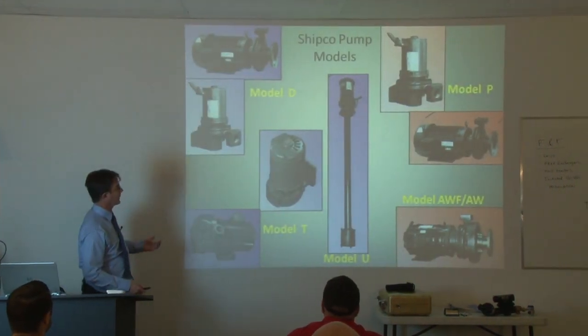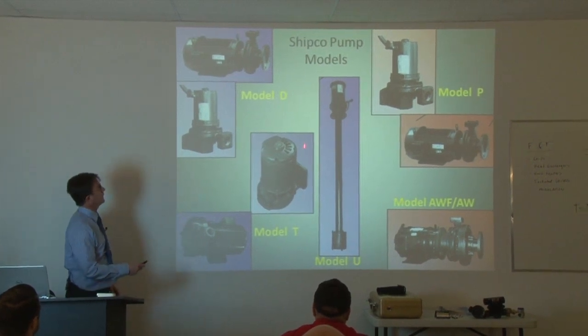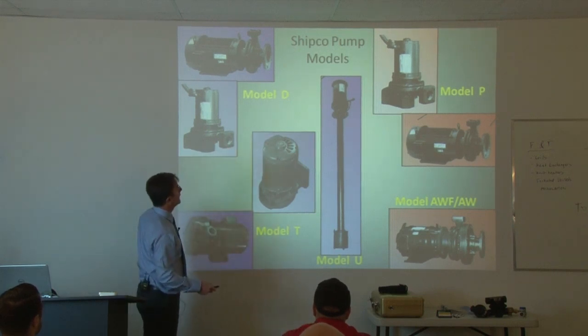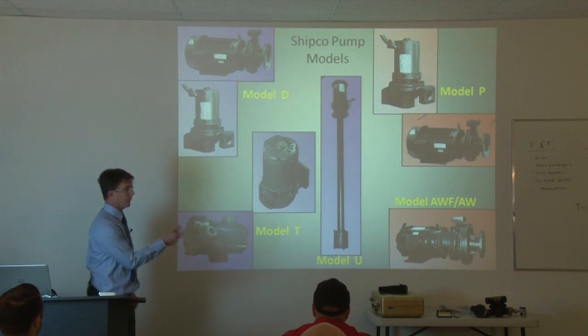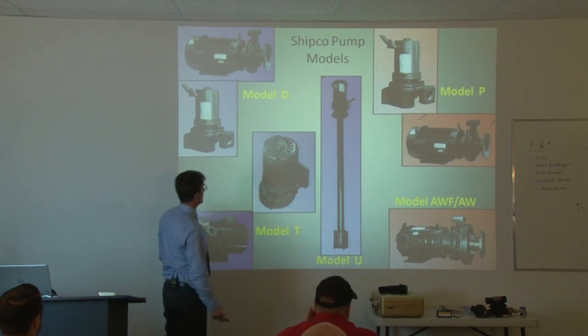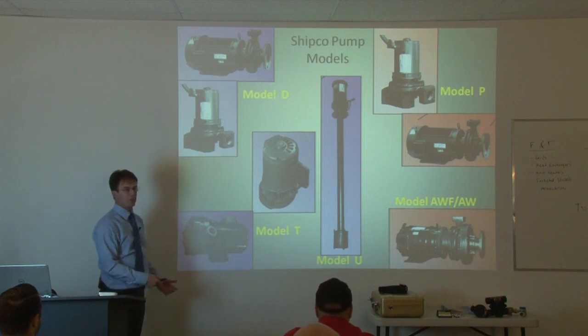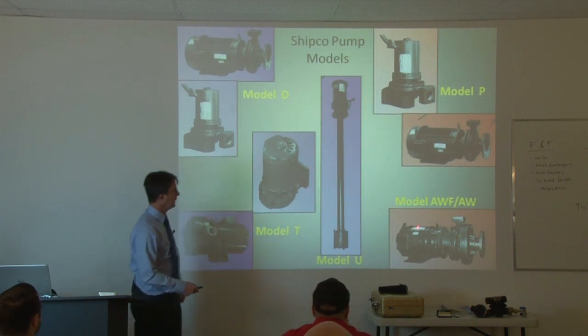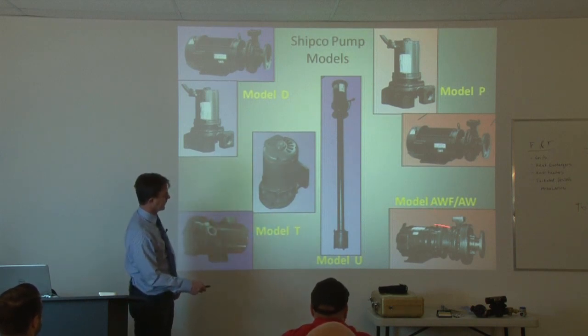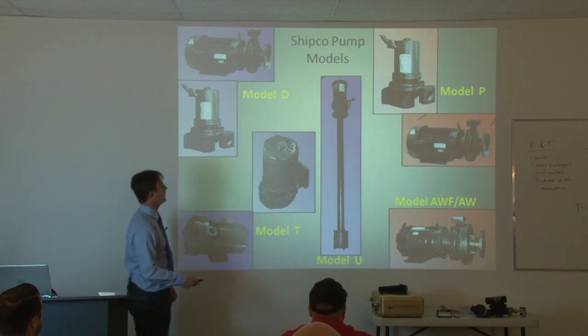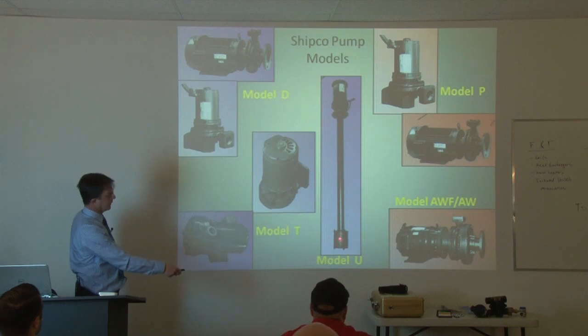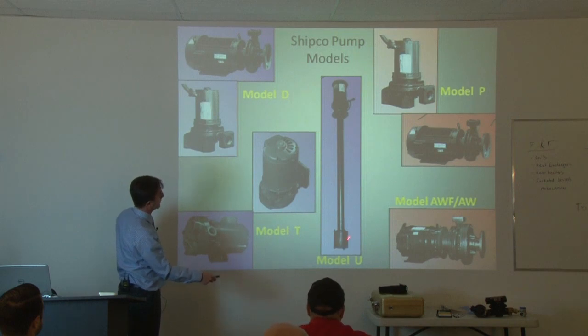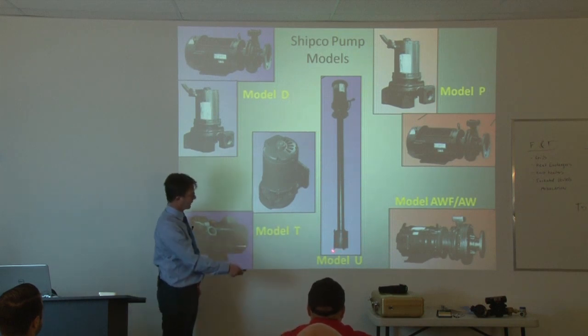Shipco pumps has a variety of different types of pumps. The Model D is probably the most common one, just for regular condensate handling applications. The Model P has a small propeller at the eye of the impeller - that's where they get the P from. Model T is their turbine type, not very common. Model AWF is for very high flows - it's a multi-stage pump. And then the Model U is for underground sump pump applications where the motor is way up high and the inlet to the pump is down several feet away.